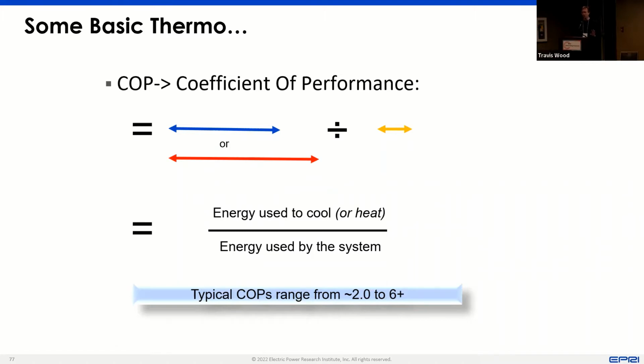So this is the heart of the coefficient of performance. There's a cooling coefficient of performance, which is the blue line, or the evaporation process, divided by the orange line, which is the compression process. And likewise, there's a heating COP, which is the red divided by the orange.